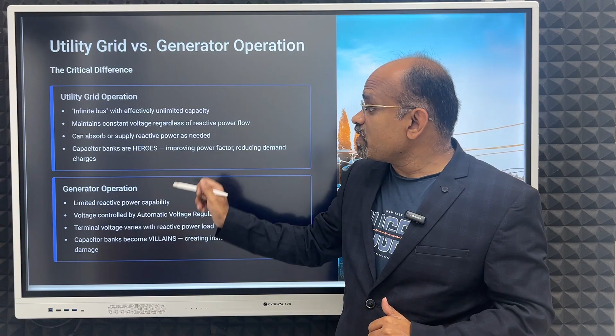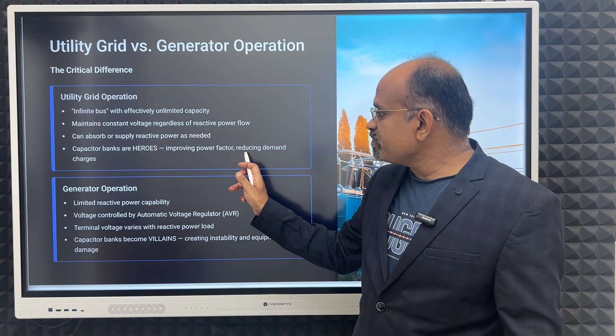So it also has capacitors. If you have seen the 400 kV or 500 kV big substations, you see capacitors hanging on the transmission line towers. So every transmission line has capacitors, and these capacitors can absorb or supply reactive power. They have made this arrangement already. Now, capacitor banks are heroes, improving power factor and reducing demand charges. In this case, it will not give load on those transmission capacitors, so it will manage. Those are the heroes.